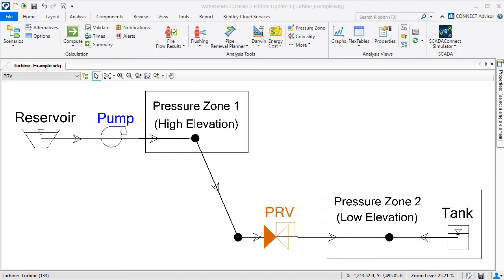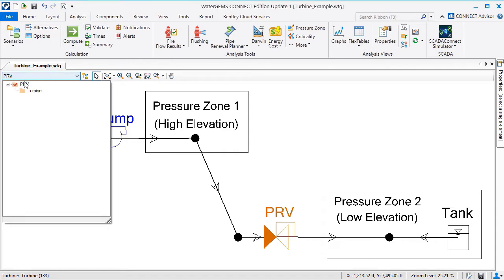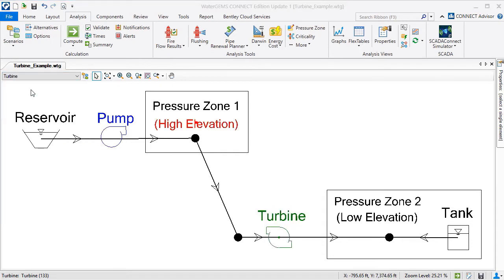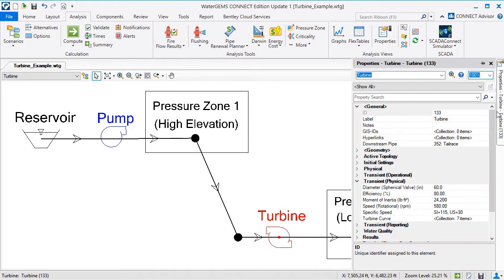Here's a sample model that uses a pressure reducing valve, which throttles flow, to limit the downstream pressure. I'll switch to another scenario that replaces the PRV with the turbine, so I can recover the energy that would be lost at the PRV. I have already entered the properties for the turbine and computed the model with a duration of 30 days.